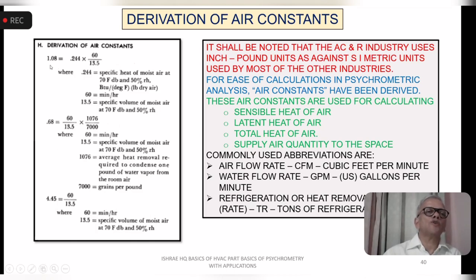1.08 is the constant used for sensible heat. When you see the Carrier system heat load calculation form, you will find this number mentioned there, 1.08. You will also find 0.68 as the number mentioned for the latent loads and 4.45 for the total heat. So here is the explanation. 0.244 is the specific heat of moist air at this condition. Then this is the conversion 60, which is 60 minutes in 1 hour, because we are talking about BTU per hour. So to calculate with CFM, or cubic feet per minute, you have to make sure it is converted to per hour. So you take the rate for 60 minutes, which is equal to 1 hour. That's why this 60 has come.